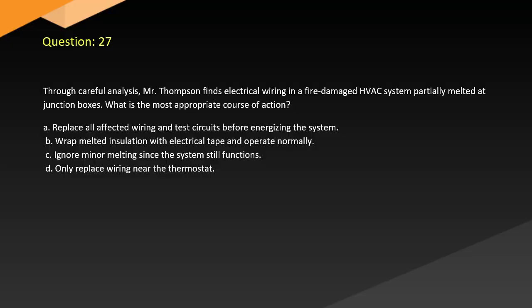Question 27. Through careful analysis, Mr. Thompson finds electrical wiring in a fire-damaged HVAC system partially melted at junction boxes. What is the most appropriate course of action? A. Replace all affected wiring and test circuits before energizing the system. B. Wrap melted insulation with electrical tape and operate normally. C. Ignore minor melting since the system still functions. D. Only replace wiring near the thermostat.